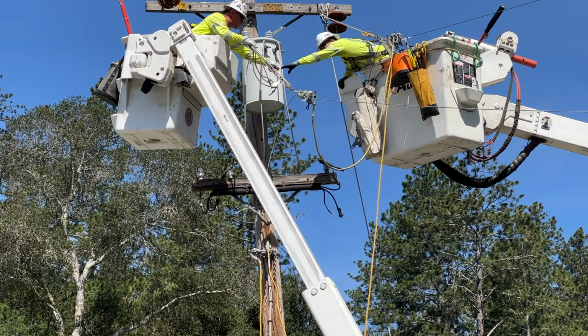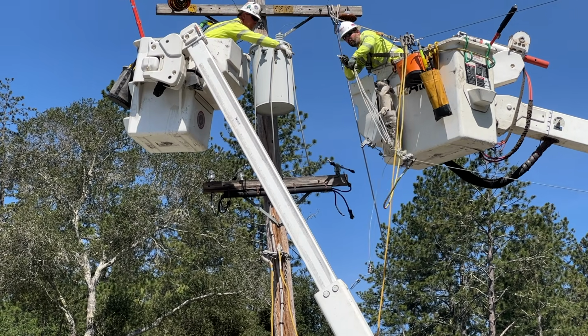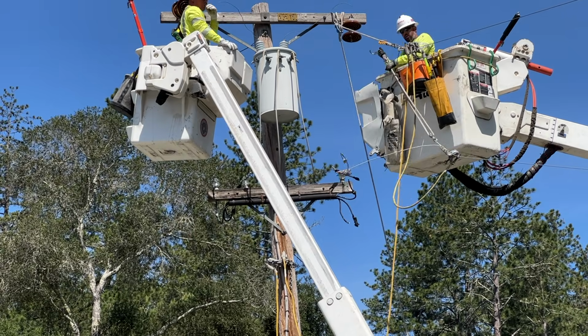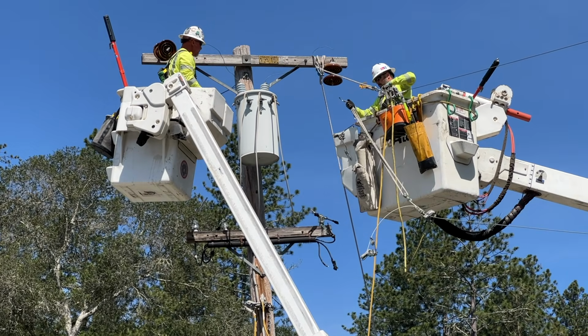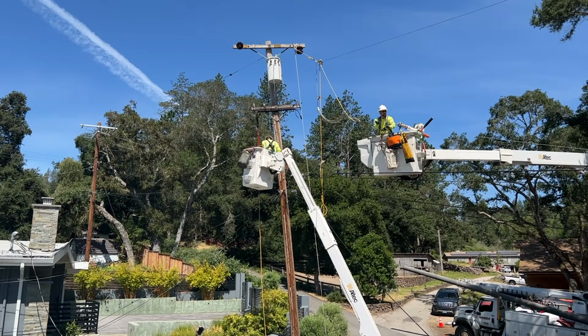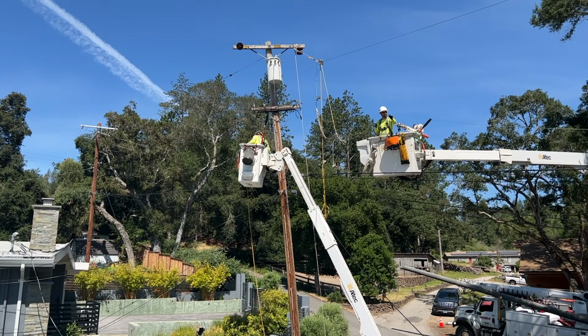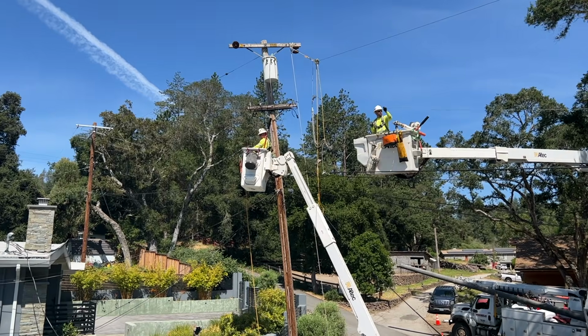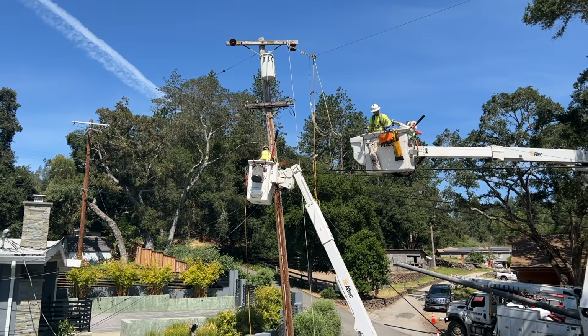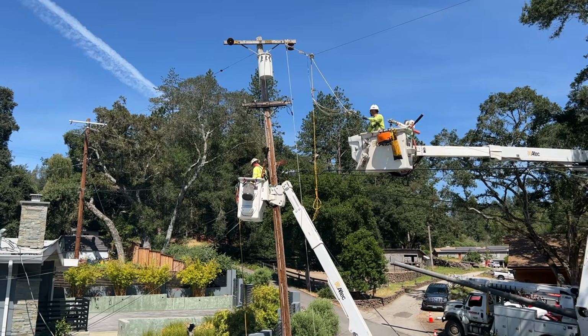Yeah, so the yellow cable's all connected to that ground rod with the handles. Those handles were clamp points that they shoved into the ground, so that if there's any stray static electricity, lightning pulses, or energizing, it'll short it right out and blow a protection and keep static off the line.